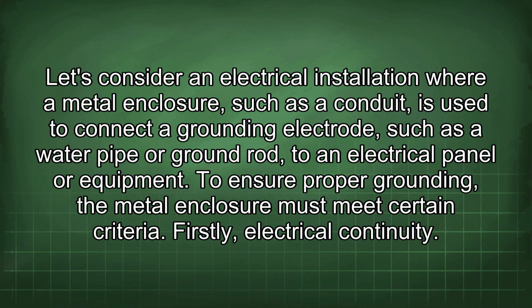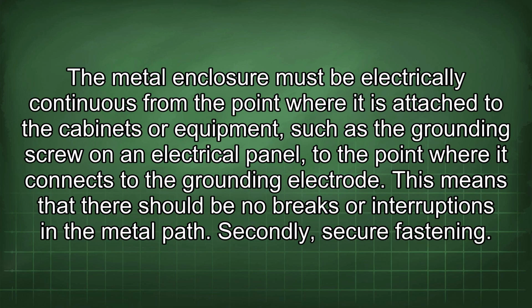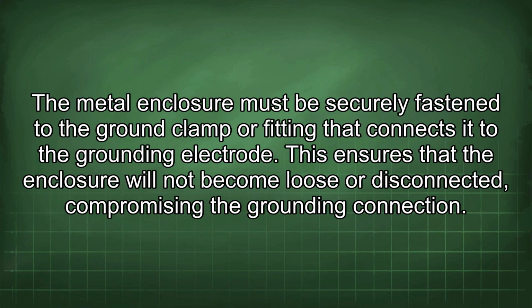Firstly, electrical continuity. The metal enclosure must be electrically continuous from the point where it is attached to the cabinets or equipment, such as the grounding screw on an electrical panel, to the point where it connects to the grounding electrode. This means that there should be no breaks or interruptions in the metal path. Secondly, secure fastening. The metal enclosure must be securely fastened to the ground clamp or fitting that connects it to the grounding electrode. This ensures that the enclosure will not become loose or disconnected, compromising the grounding connection.